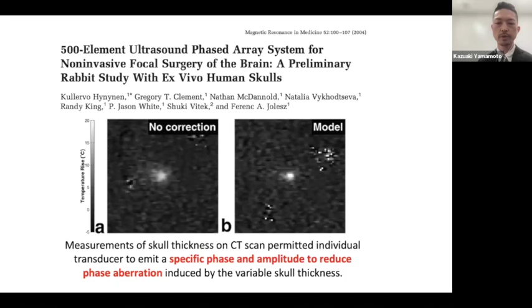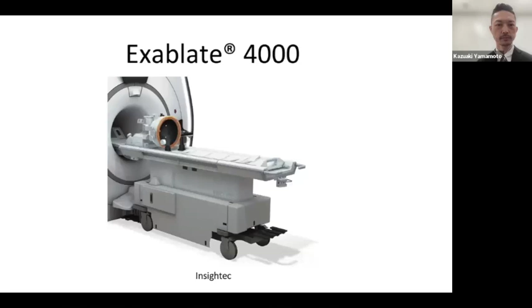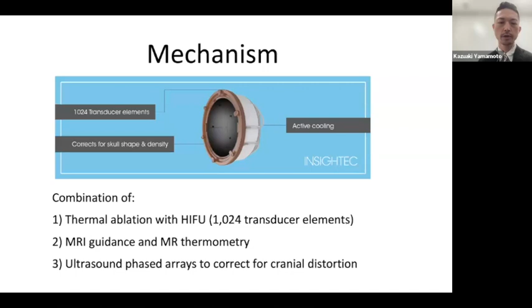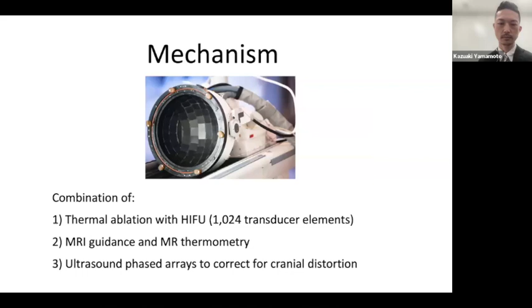This is the most widely used focused ultrasound device today, Exablate Neuro by Insightec. The system integrates thermal ablation via high-intensity focused ultrasound, MRI guidance, MR thermometry, and a hemispheric array of 1024 transducer elements for phase correction. The principle is similar to burning paper with a magnifying glass. Beams are focused precisely to hit the target tissue.